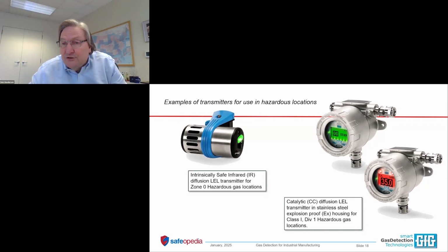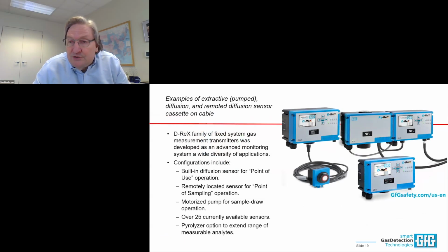That's how we design portable instruments. I'm sure most of you have heard the term intrinsic safety for portable instruments that are used to measure combustible gas and other hazards. Well, we have the same option available for fixed gas detection gas transmitters. So here's an example of an intrinsically safe combustible gas transmitter where, because there is no possibility of the release of enough energy to be the source of ignition for the combustible gas that might be present, I don't have the same requirements for super expensive certified stainless steel explosion-proof conduit. I can use electrically compliant conduit that is a whole lot less expensive and easier to install. So those are your options there.